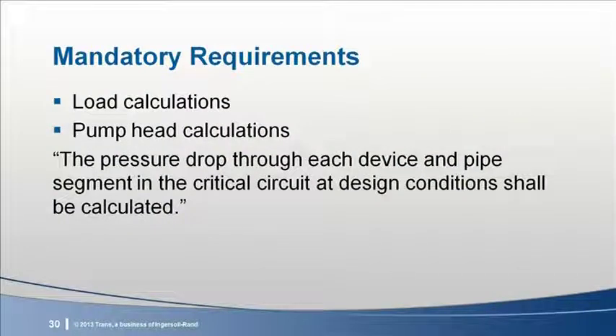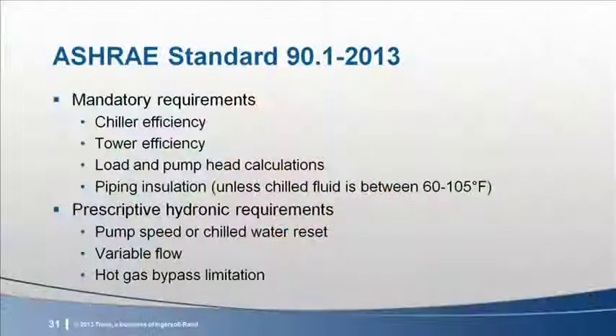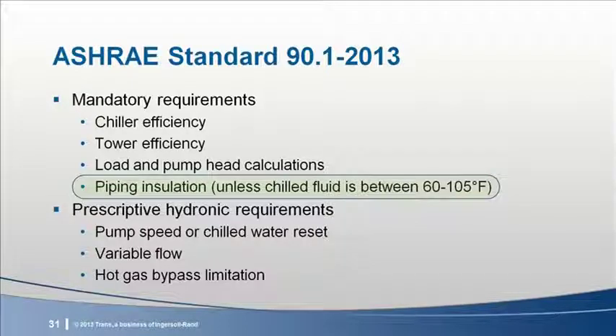Here's an excerpt of what 90.1 says. The pressure drop through each device and pipe segment in the critical circuit at design conditions shall be calculated. Now that it's common to have VFDs on pumps, the drive is used to balance the system. But if your pump VSD has to be turned down to 45 Hz at the design point, not much additional turn down is available. Likewise, if your load calculation is poor, especially if it's dramatically oversized, your chiller plant won't be as efficient as it could have been and also overpriced. I'm going to skip over piping insulation as there were no changes in this area in the 2013 version.